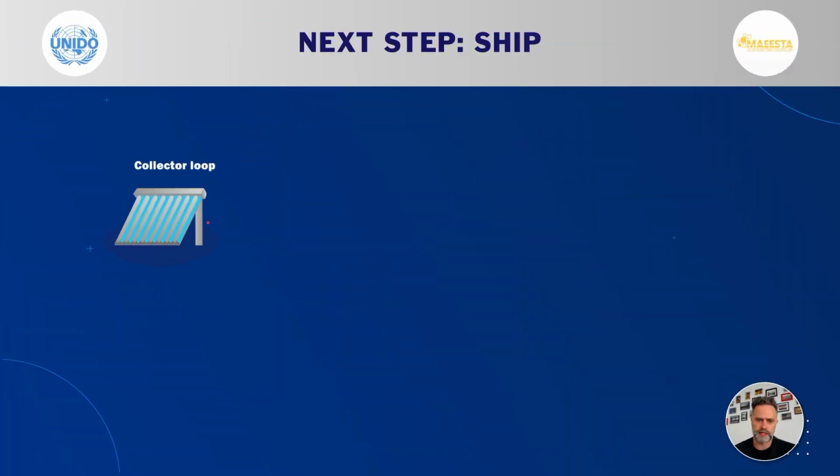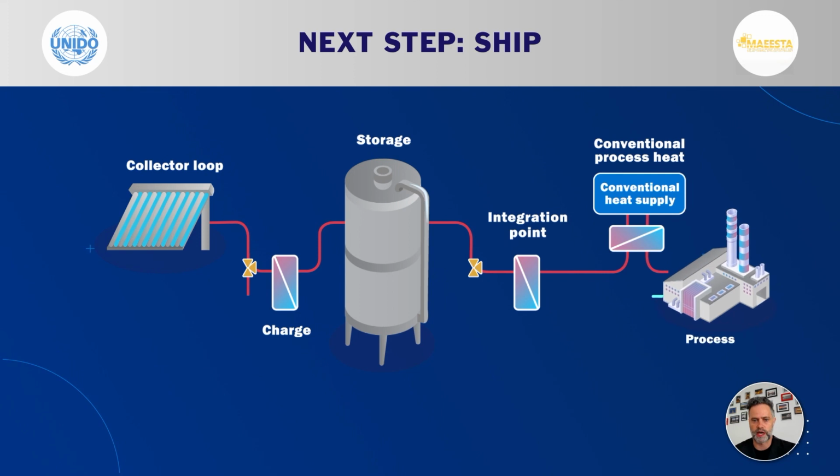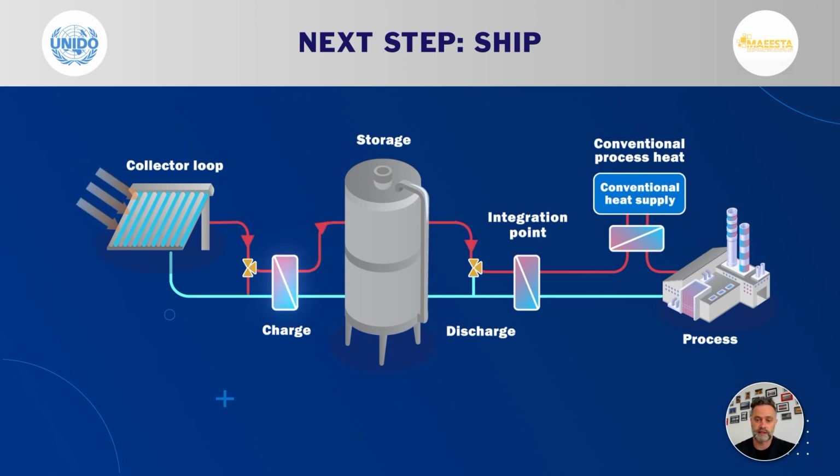All these steps are necessary to optimize the system: a collector field necessary to supply the demanded energy, and a storage tank. You might ask why we need a storage tank. Well, it is obvious that in most cases the production is not scheduled on the availability of the sunshine or the forecasted thunderstorm. So we harvest the energy when the sun is shining, store it in a tank, and use it whenever we need the energy.